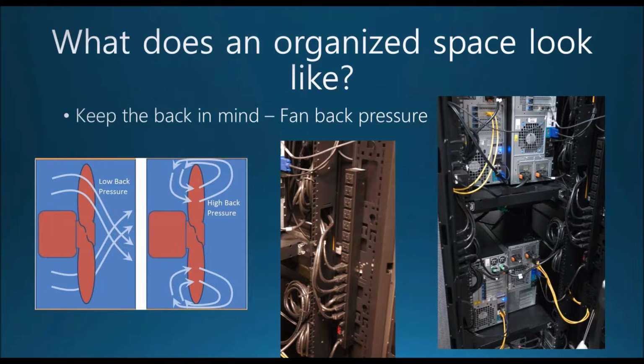Fan back pressure is a big word, but it basically means this: if you have a server sitting on the floor shoved up against a wall, the fan blows out heat but doesn't have enough force to push that heat away from the unit quickly. High back pressure forces the heat against the wall, and it actually gets sucked back into the fans, regenerating some of that heat.